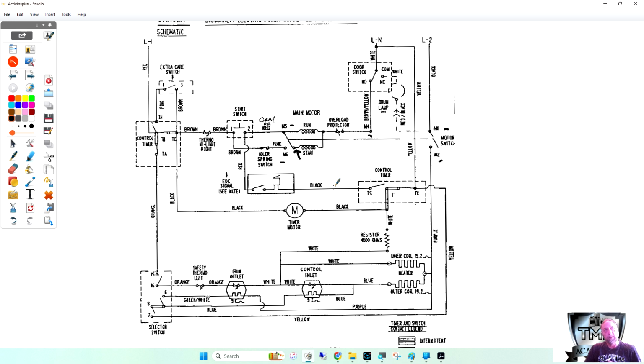It may be because all the ones with the M's showing in this diagram now have wires that are connecting to the motor from someplace else in the machine. M3 does not have a wire coming from the timer or from the door switch or anything that goes to M3. The only wire in M3 is the motor winding inside the motor, but that's what's connected there.